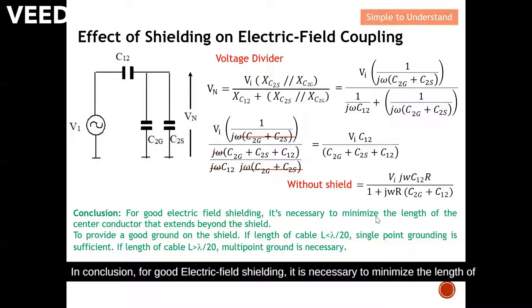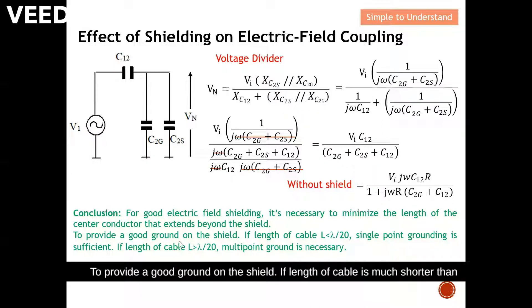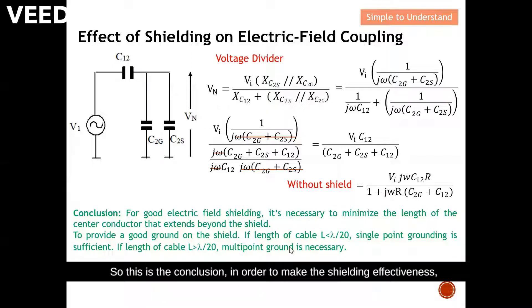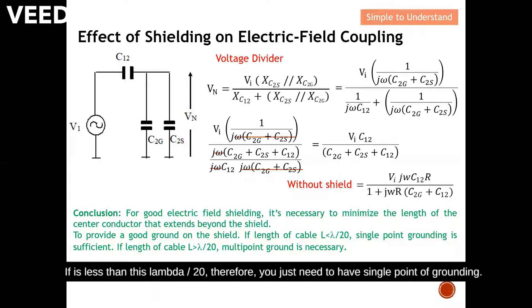In conclusion, for good electric field shielding it is necessary to minimize the length of the center conductor that extends beyond the shield, and to provide a good ground on the shield. If the cable length L is much shorter than λ/20, single-point grounding is sufficient, though I still encourage two-point grounding. If the cable length L is greater than λ/20, multiple-point grounding is needed to achieve sufficient shielding effectiveness.